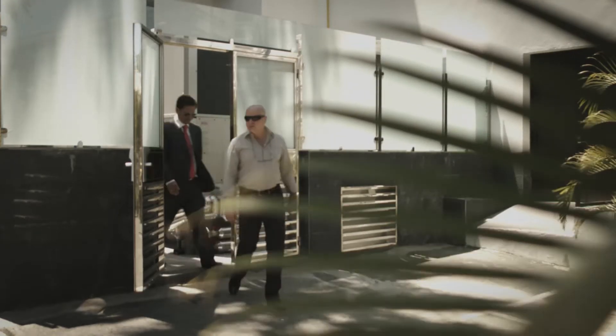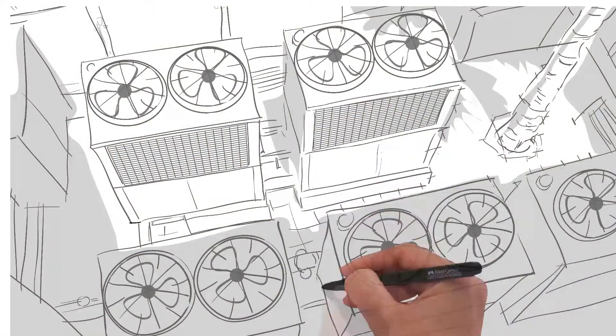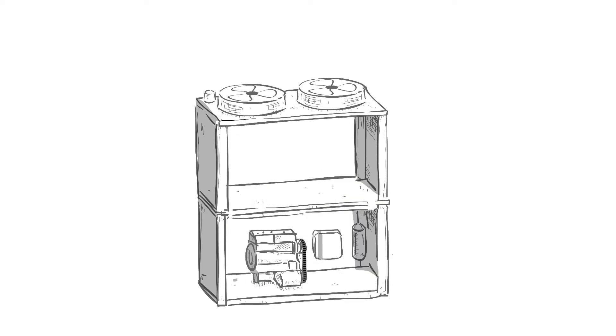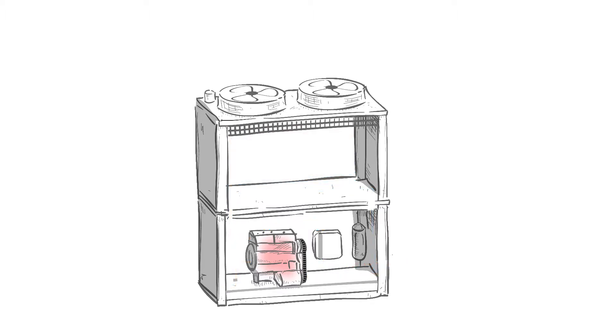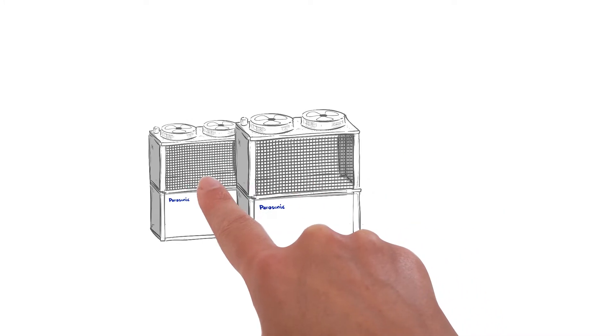But how does this heat pump actually work? The Eco-G Panasonic VRF gas heat pump supplies a unique technology which cools and heats with maximum efficiency. The Panasonic VRF GHP is powered with natural gas instead of electricity. The refrigerant is moved within the system piping thanks to two compressors driven by an internal combustion engine. The combination of different heat pump sizes offers the perfect match to meet customers' needs.